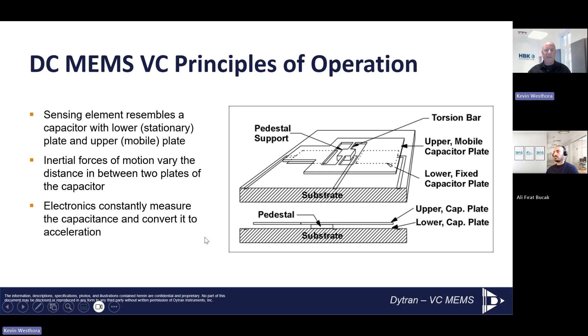We gas damp that space in between with nitrogen so it's not free to vibrate uncontrollably. As that plate moves compared to the lower plate, it changes the capacitance between the two plates, and that change is extremely linear. As you rotate or shake the accelerometer, it changes that capacitance. That's why these are limited - they can measure DC frequency because sitting still it'll measure that capacitance, but it's limited in how many Gs you can measure. The maximum we offer at Dytran right now is 400 Gs for this technology. So that's a bit of an overview of the capability and technology of a DC MEMS accelerometer.